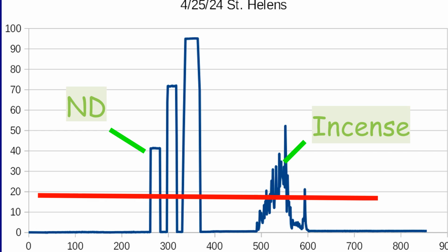You can see here that we've got an ND2, an ND4, and an ND8. And the ND8 is almost 100% opacity. It's really 95%. However, we're only interested in the 20% as far as smoke is concerned.